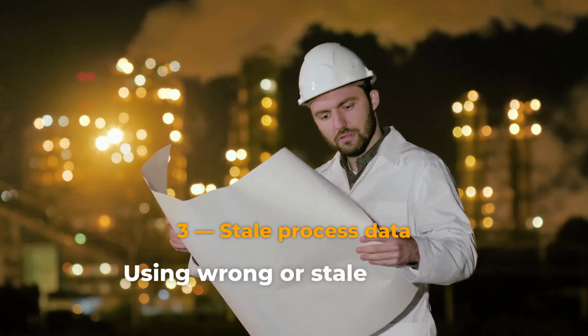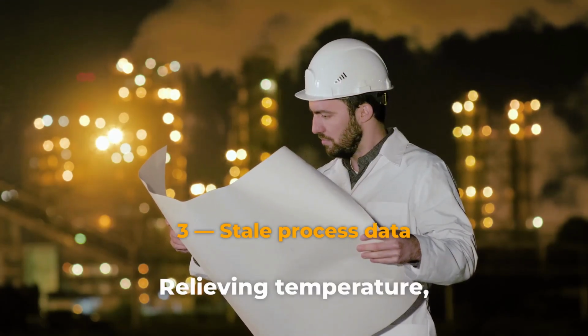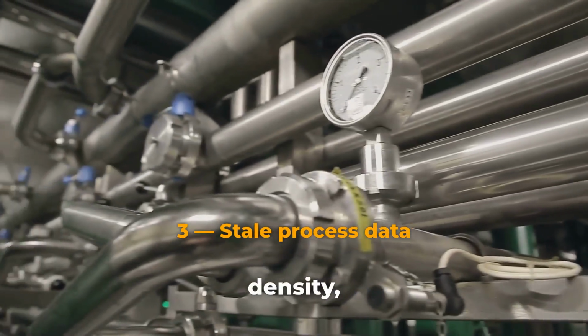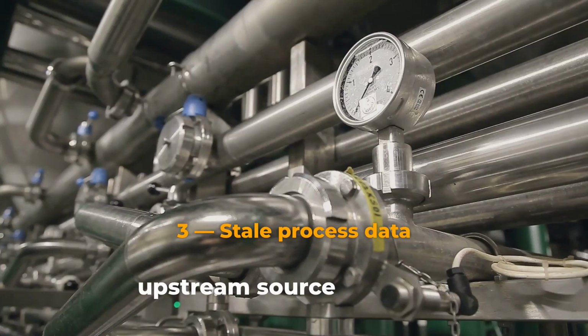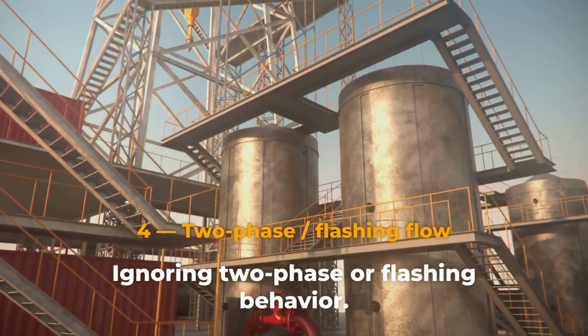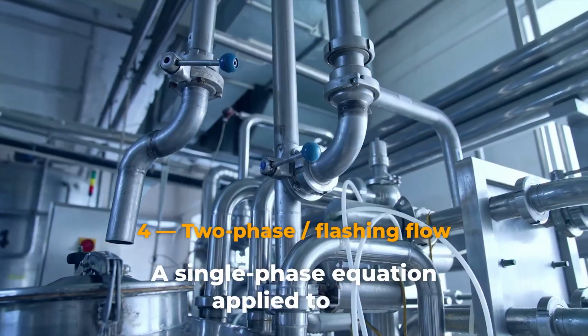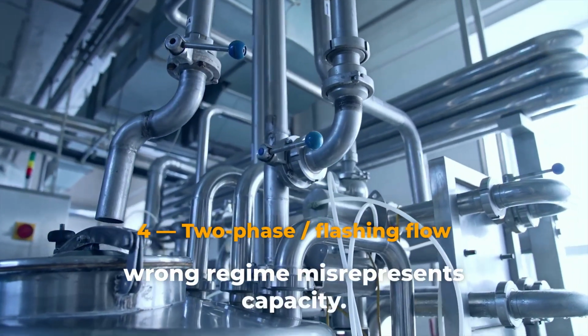Using wrong or stale process data. Relieving temperature, molecular weight, density, phase behavior, upstream source pressure, or heat input. Ignoring two-phase or flashing behavior. A single-phase equation applied to the wrong regime misrepresents capacity.